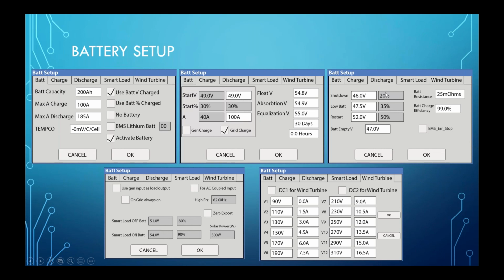You have different discharge values for lead acid versus lithium. Just to put an example, SimpliPhi, one of our partners, I believe their cutoff is 51 volts, whereas some of our other ones, Fortress and some of the other lithium iron batteries that we have partnered with, go down to like 47, 48 volts, and that's allowed by their BMS. So just keep that in mind as you're going through that, especially if you're using a battery that does not have communications. Resistance efficiency is pretty straightforward. You don't necessarily have to change it unless requested by the manufacturer.